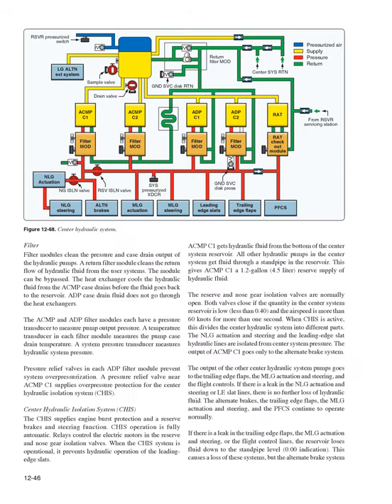Filter modules clean the pressure and case drain output of the hydraulic pumps. A return filter module cleans the return flow of hydraulic fluid from the user systems. The module can be bypassed. The heat exchanger cools the hydraulic fluid from the ACMP case drains before the fluid goes back to the reservoir. ADP case drain fluid does not go through the heat exchangers.